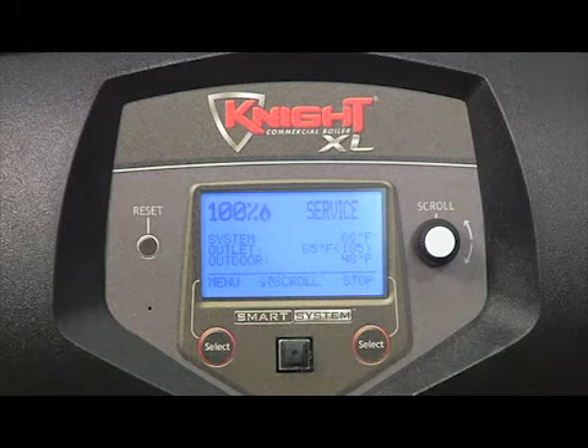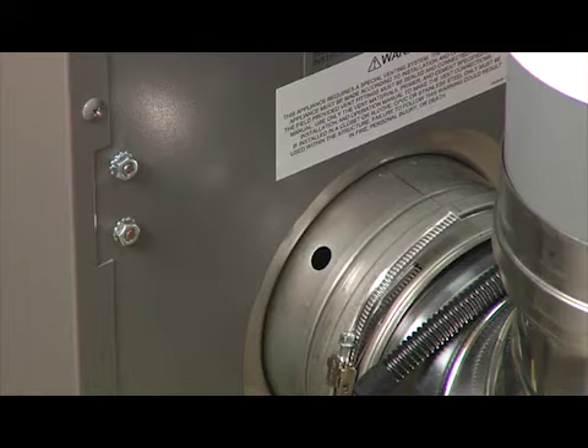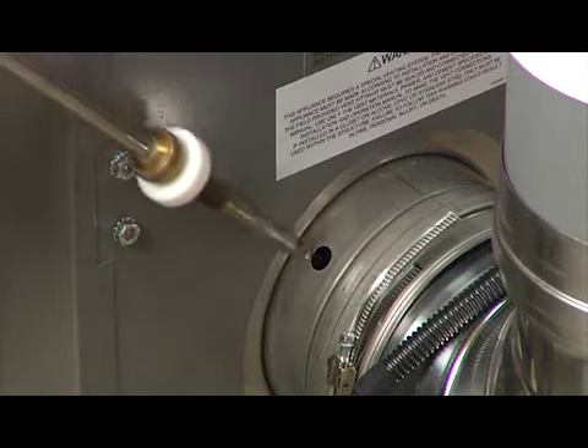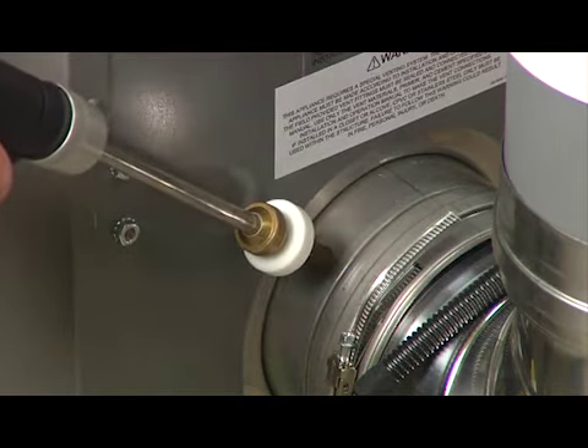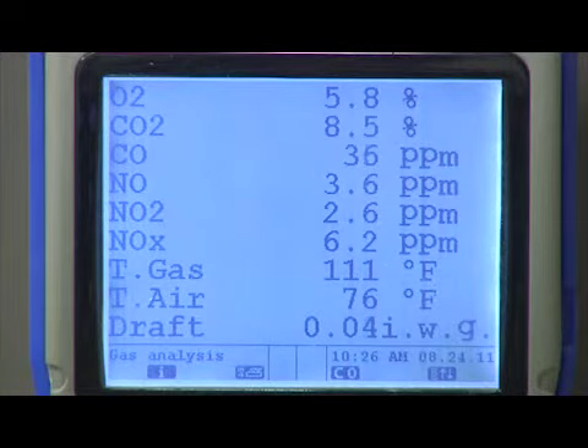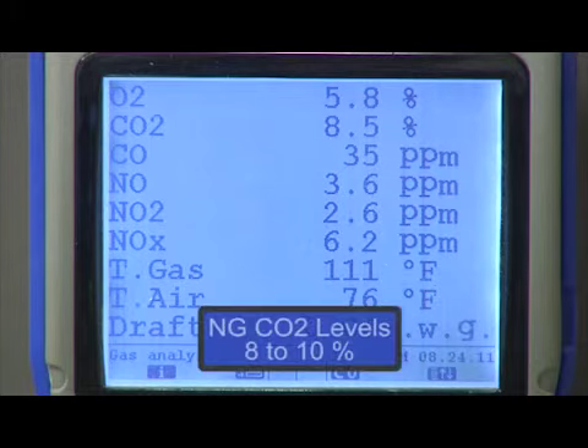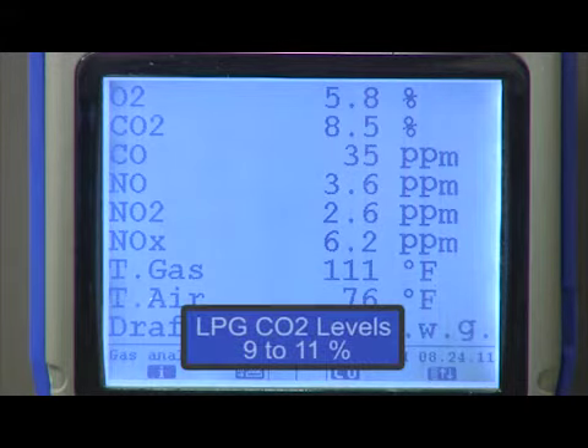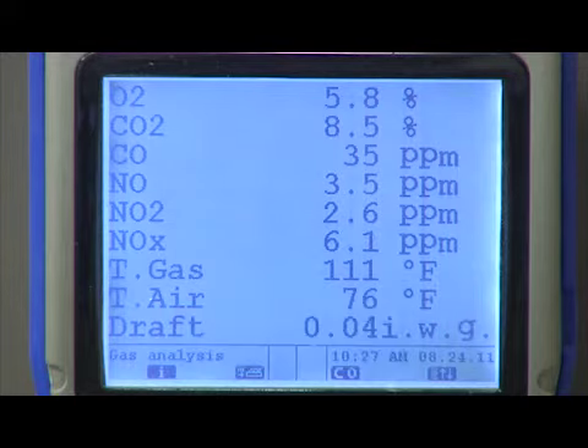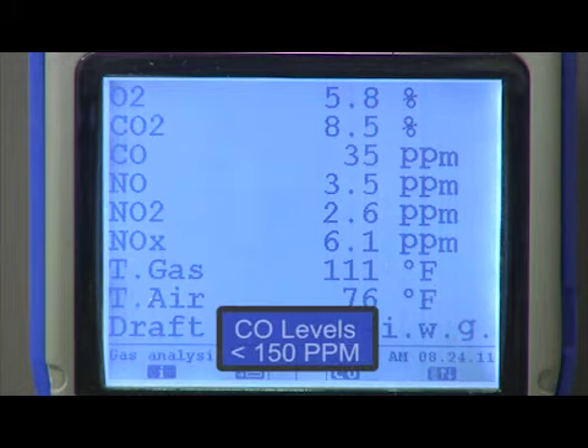Once the unit has modulated its firing rate up to 100%, insert the probe from a combustion analyzer into the hole left by the removal of the flue sensor and measure the combustion. For natural gas models, the carbon dioxide or CO2 levels should be between 8 to 10%. For propane gas models, the CO2 levels should be between 9 to 11%. For both natural and propane gas models, the carbon monoxide or CO levels should be no more than 150 parts per million for a properly installed unit.